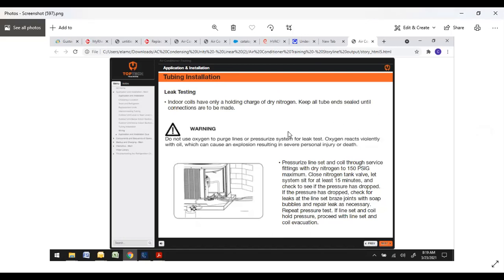Leak testing. Indoor coils, they obviously come with a charge. Do not use oxygen to purge lines or pressurize the system for leak testing. Oxygen reacts violently with oil, which can cause an explosion. Pressurize the line set and coil through service fittings with dry nitrogen to 150 psig maximum. If you're just doing a line set and coil, you could probably go higher, truthfully. They're being conservative there.